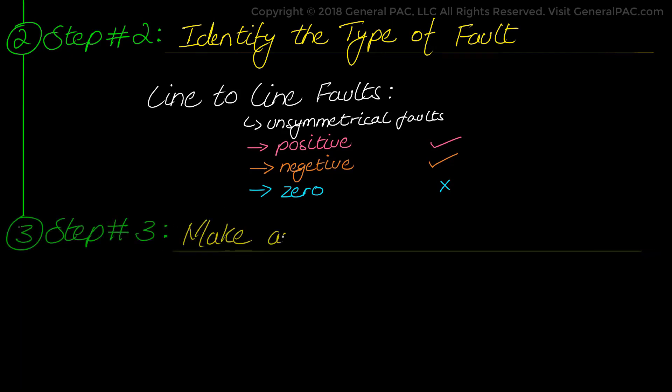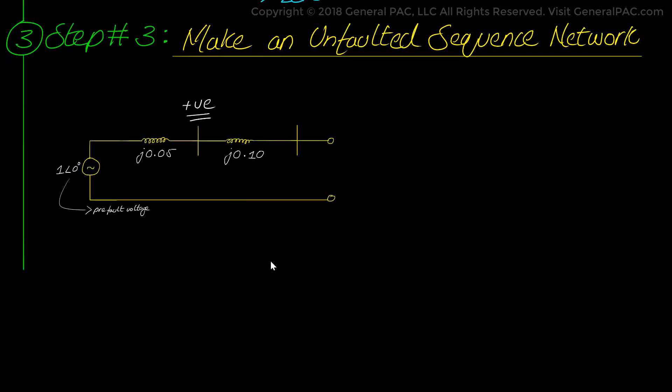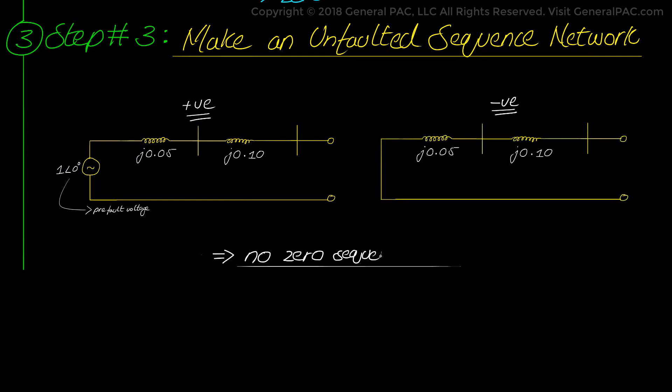Next, we move to step number 3 which asks us to make a sequence network from the per unit converted system. So we draw the positive sequence network and we also draw the negative sequence network. Again, we don't have a zero sequence network because we have a line-to-line fault which does not have a ground mode.